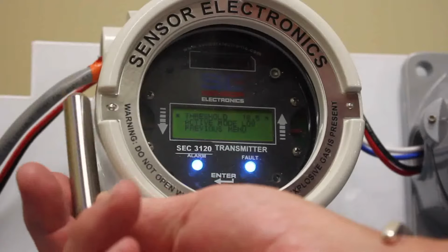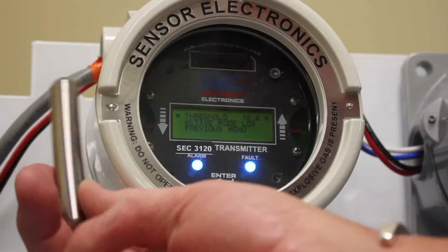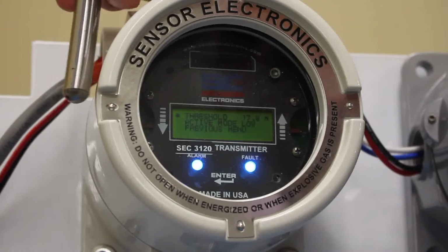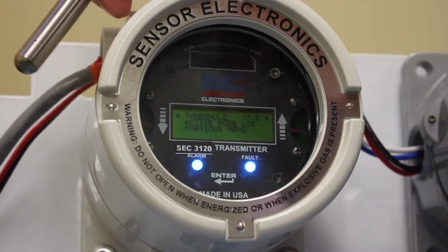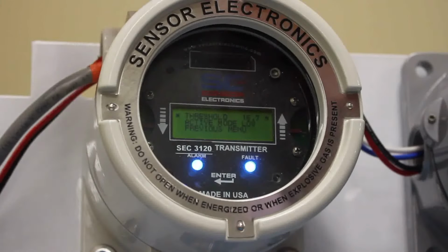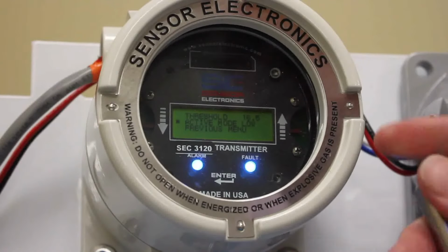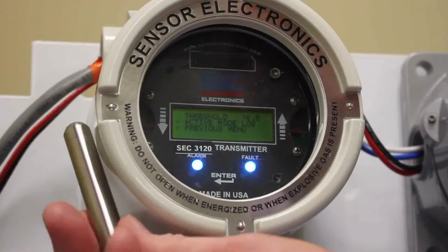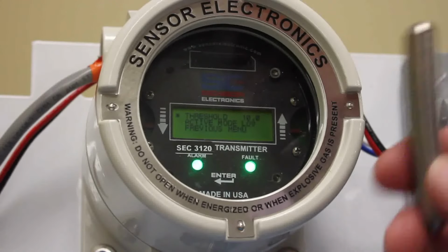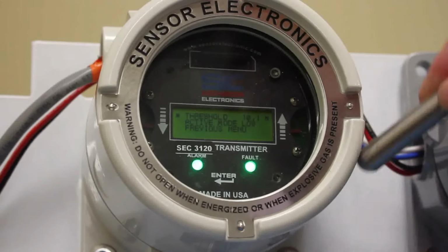What's unique about the oxygen sensor is that it really has two low alarm set points. So we'll go in after we get the low set correctly. There we go. And it's set for active low, which is correct. And then go to Previous Menu, Save, and we'll go to Mid Alarm. And in that we want to set for 19.5% by volume.